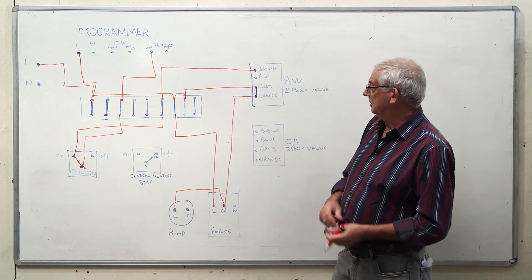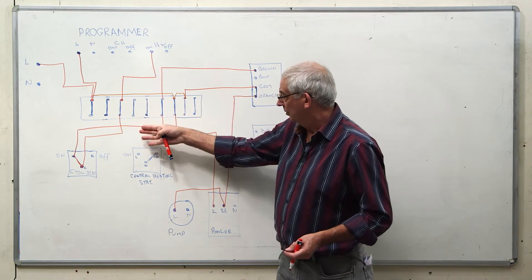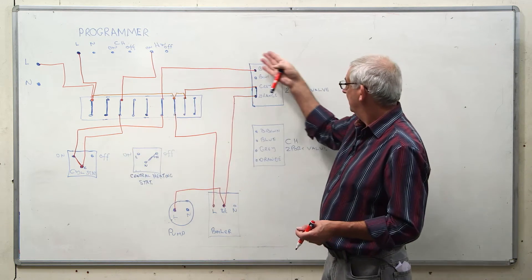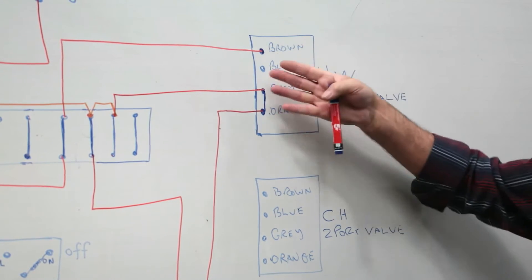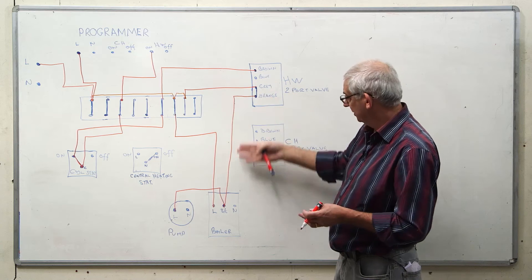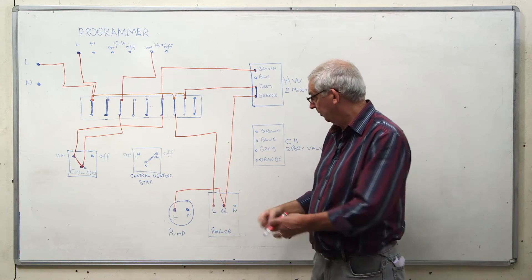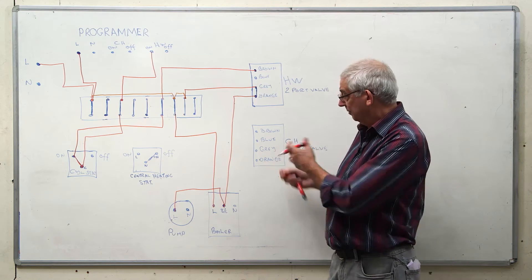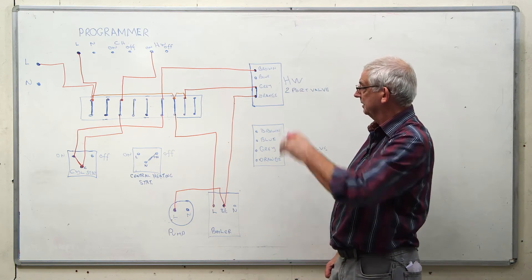So now what we've got is a situation where calling for hot water, cylinder stat is made, the micro switch is closed because the valve is now opened, micro switch closed, sends a live down to the boiler, the boiler starts up, starts the pump running and we've now got hot water flowing through the system.